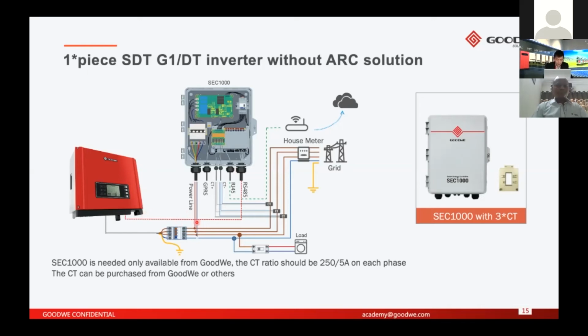So you can find here the inverter connected to the house meter, connected to the grid, and the SEC1000 power meter, with the power line connected to each phase, and the CTs connected to each phase, and here the RS485 cable connects to the inverter. Then you can control the inverter output power. So in this case, you need to use the SEC1000 also with three CTs. The CTs that work with the SEC1000 you can buy from GoodWe, and also from your local market.